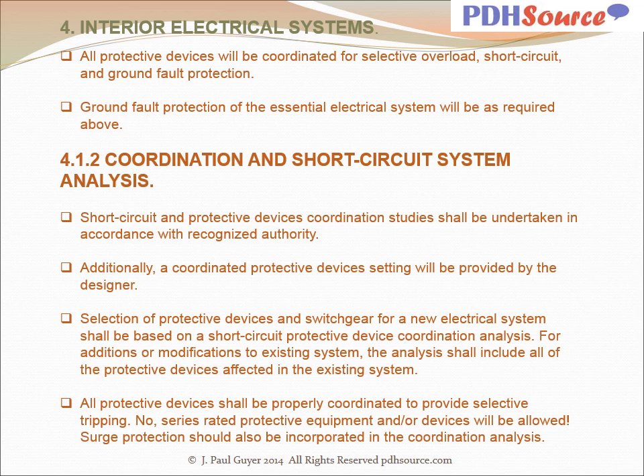Selection of protective devices and switchgear for a new electrical system shall be based on a short circuit protective device coordination analysis. For additions or modifications to existing systems, the analysis shall include all of the protective devices affected in the existing system. All protective devices shall be properly coordinated to provide selective tripping. No series rated protective equipment and/or devices will be allowed. Surge protection should also be incorporated in the coordination analysis.